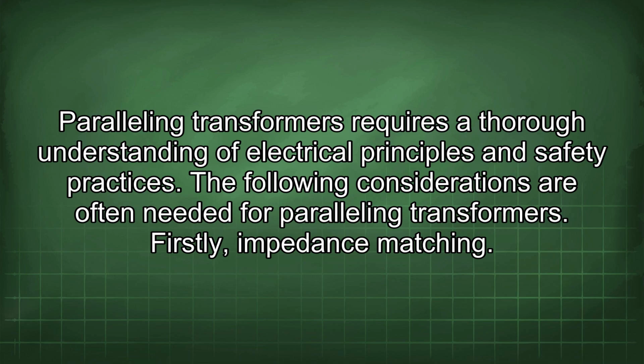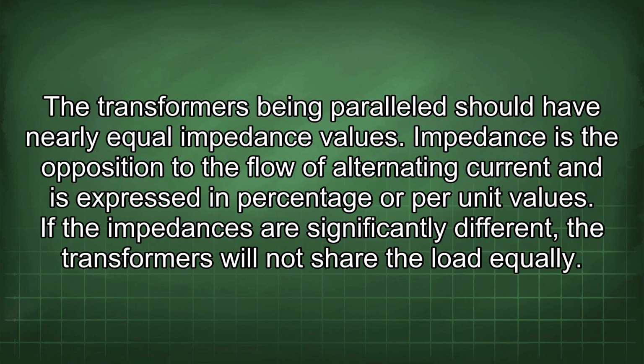The following considerations are often needed for paralleling transformers. Firstly, impedance matching. The transformers being paralleled should have nearly equal impedance values. Impedance is the opposition to the flow of alternating current and is expressed in percentage or per unit values. If the impedances are significantly different, the transformers will not share the load equally.